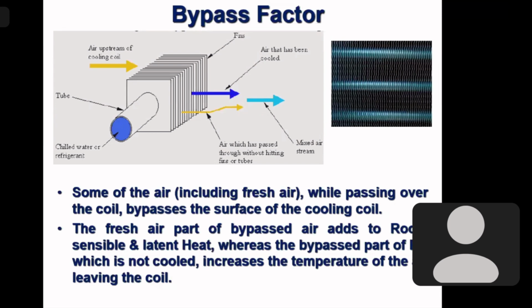It comes into the room again through the cooling coil by bypassing the cooling coil. If the bypass factor is 12%, then 88% of the air, even the outside hot air, we will cool in the cooling coil, but 12% manages to bypass the cooling coil and comes straight into the room and adds both sensible and latent heat to the room. So we have to take care of that. So you know what the bypass factor is, and the return air also, a bit of it bypasses, a similar 12%.